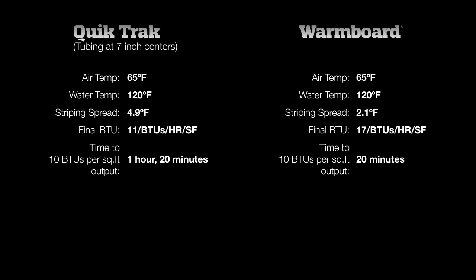WarmBoard reached the desired 10 BTU output in 20 minutes, while Quik Trak took 4 times longer. And remember, Quik Trak has nearly double the amount of tubing, which means almost twice the material costs and the labor to install it.